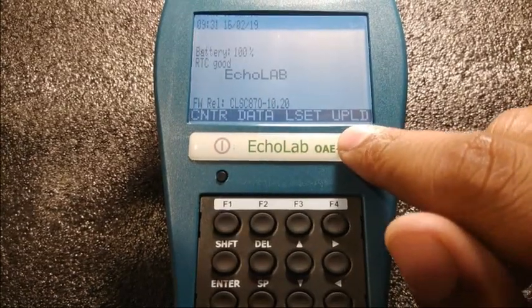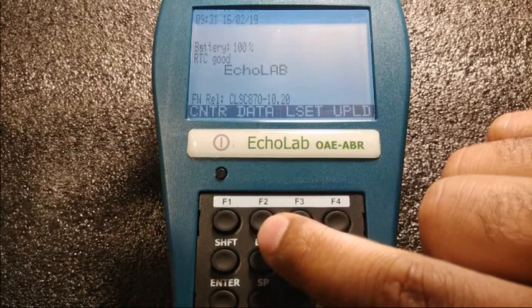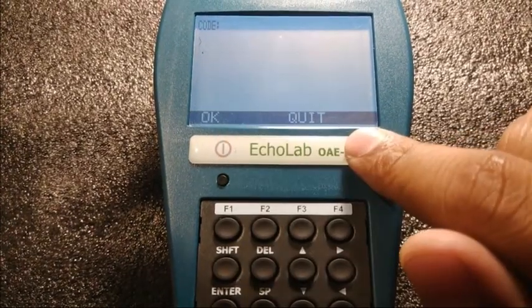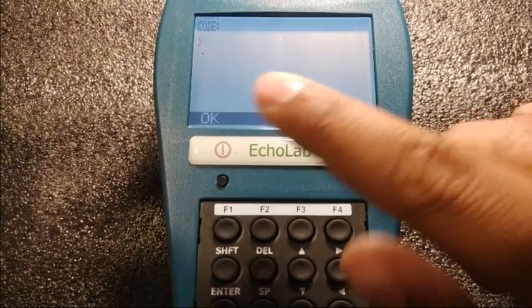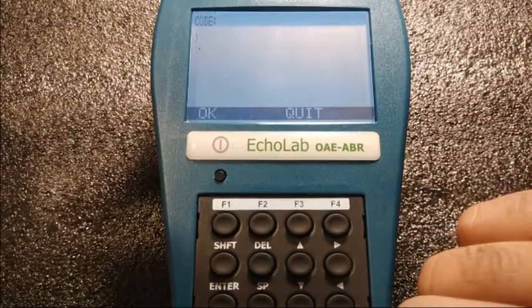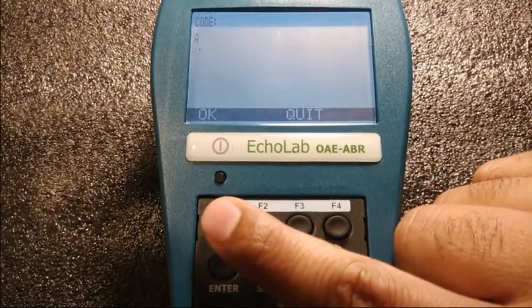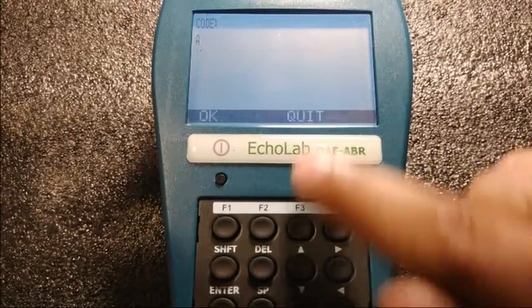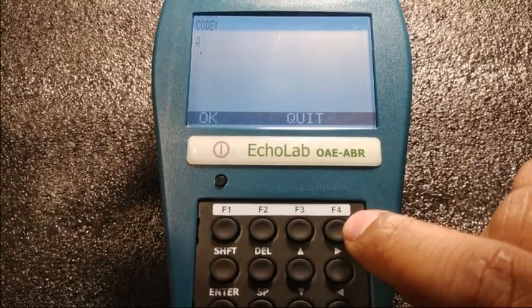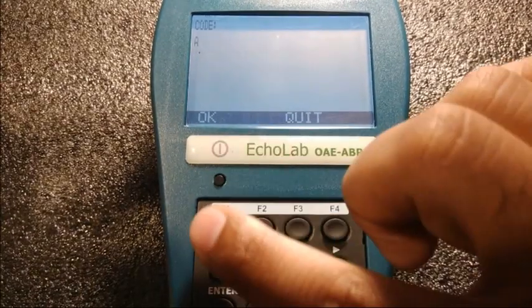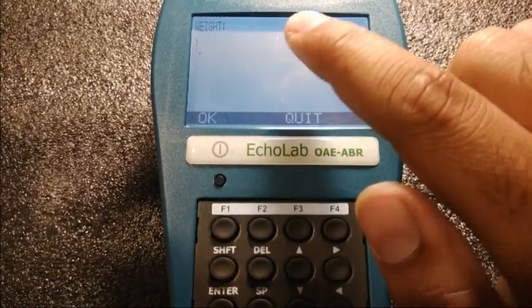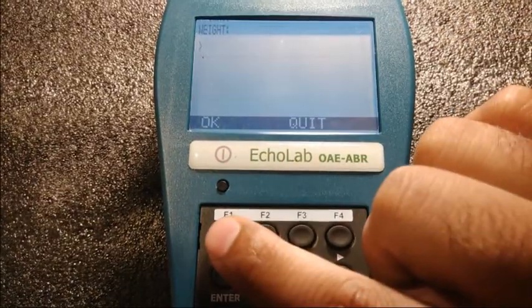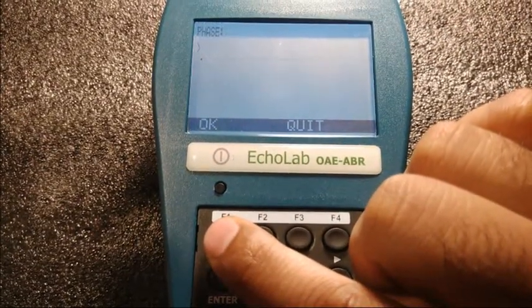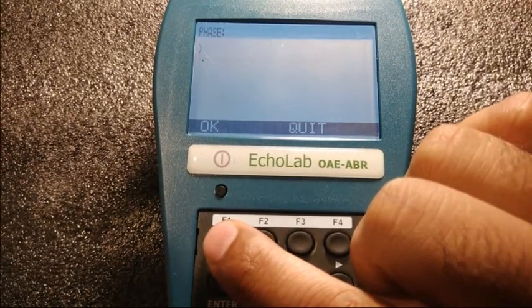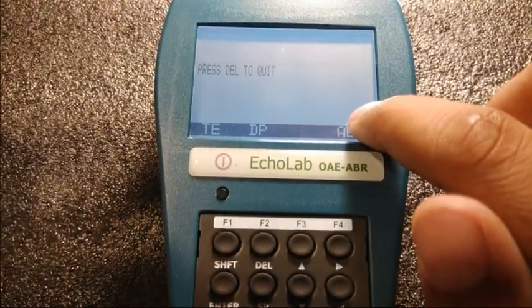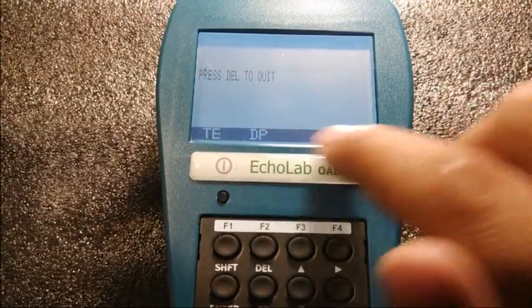So let's start it. You see data, it's above F2. So I will press F2. We will go into the menu. Now it asks for a code. Put any value that you want. I'm putting A and then I'm pressing F1 in order to OK. If I press F3 it will quit, and F2 and F4 are not functional at this moment. Now I'll press F1. I go further in the menu. It asks for the weight. I'm skipping it by pressing F1, and then it asks for the phase. I'm skipping it by pressing F1 again. Now you can see this is the test menu where you can see TE, DPI and ABR.